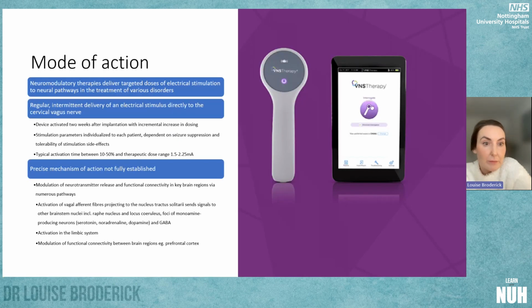So briefly, with respect to the mode of action, vagus nerve stimulation therapy falls under the umbrella of neuromodulatory therapies, which work by delivering a targeted dose of stimulation to a neural pathway. The VNS device itself delivers a regular and intermittent electrical stimulus directly to the cervical vagus nerve. Typically, after the device is implanted, there's a bedding down period, and then the device is activated 2 weeks later with incremental increase in the dosing. Stimulation parameters are individualized to every patient, and this will depend on the dose required to achieve adequate seizure suppression, but also tolerability of side effects of stimulation, which becomes relevant when we get on to talking about problems that can be encountered.